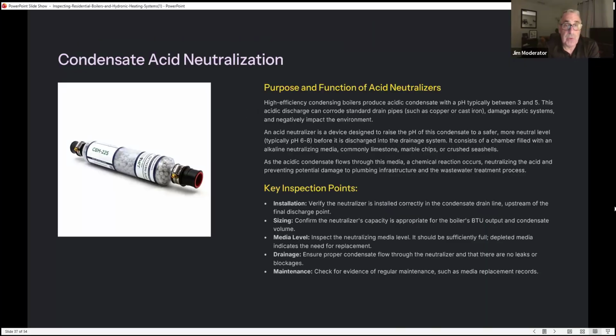Condensate acid neutralizer: the purpose and function of acid neutralizers. Again, high efficiency boilers produce acid condensate with a pH typically between 3 and 5. This acidic discharge can corrode standard drain pipes such as copper and cast iron, damage septic systems, and negatively impact the environment. An acid neutralizer is a device designed to raise the pH of this condensate to a safer, more neutral level, typically a pH of 6 to 8, before it is discharged into the drainage system.